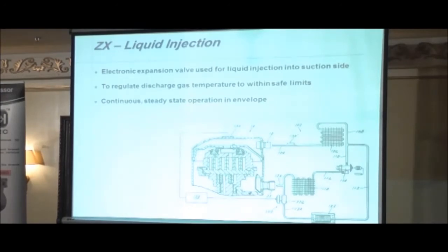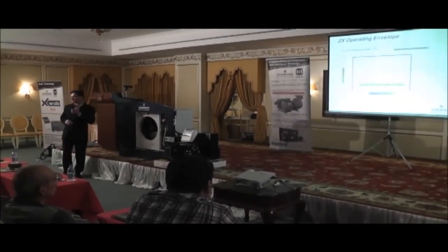So, on the medium temp units, we have suction line liquid injection, and as I mentioned before, this is very similar to demand cooling. So I've got a very simple diagram here. All we're doing is taking liquid from the liquid line, expanding it through an expansion valve, and we have a mixture of liquid and gas that we introduce into the suction line. So we're keeping the gas cool in the compressor to prevent the compressor from overheating. This is the operating limit.